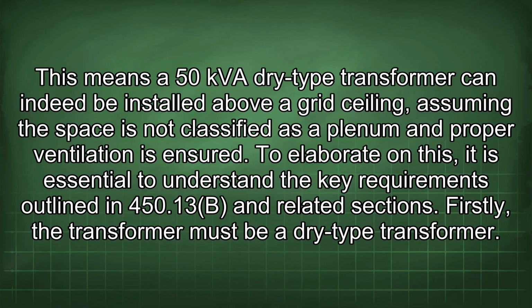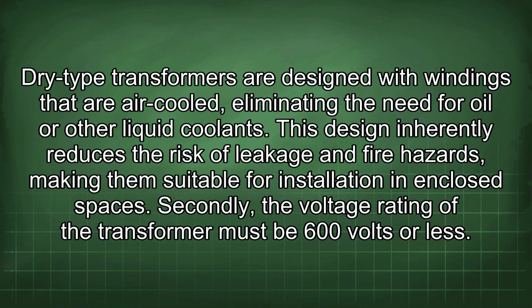To elaborate on this, it is essential to understand the key requirements outlined in 450.13(b) and related sections. Firstly, the transformer must be a dry-type transformer. Dry-type transformers are designed with windings that are air-cooled, eliminating the need for oil or other liquid coolants. This design inherently reduces the risk of leakage and fire hazards, making them suitable for installation in enclosed spaces. Secondly, the voltage rating of the transformer must be 600 volts or less.